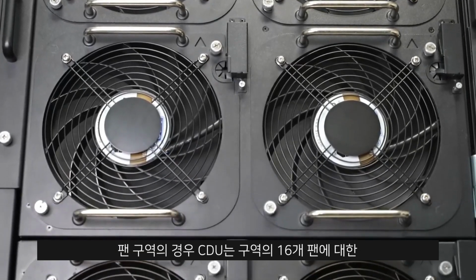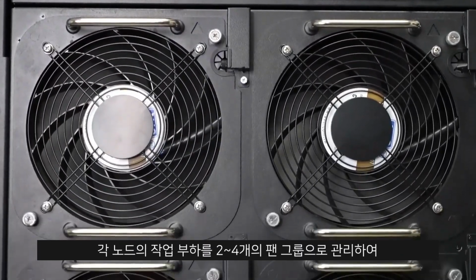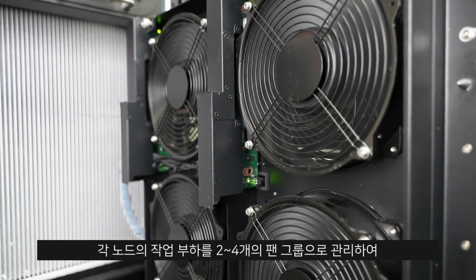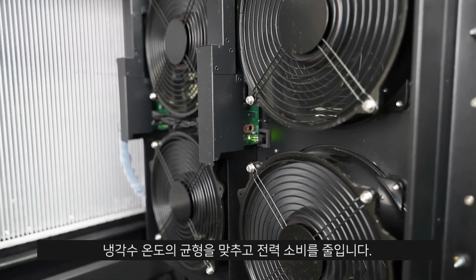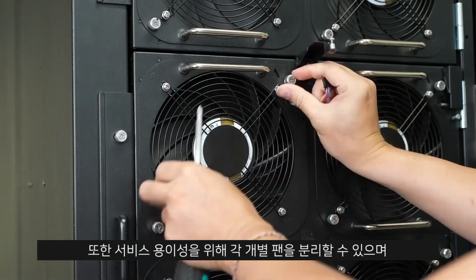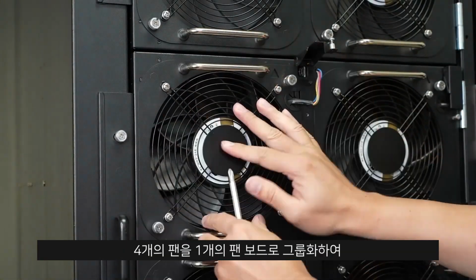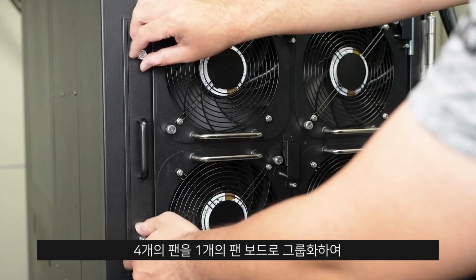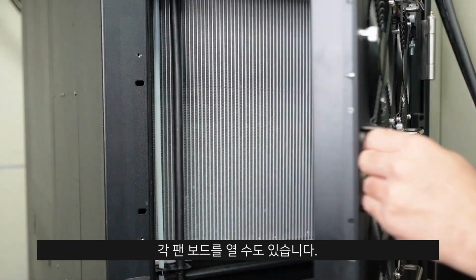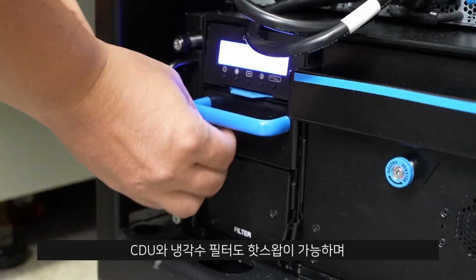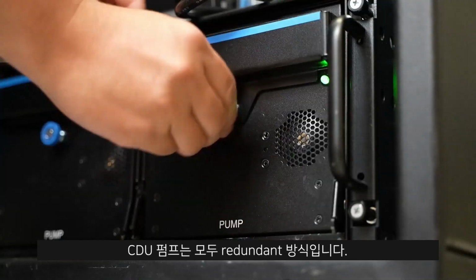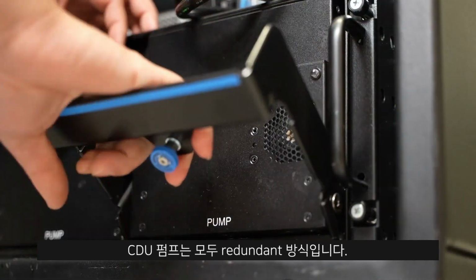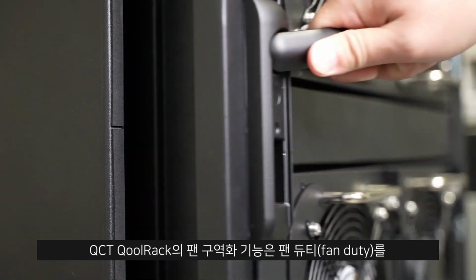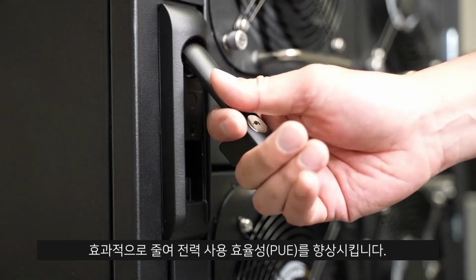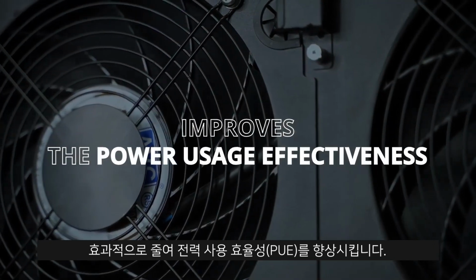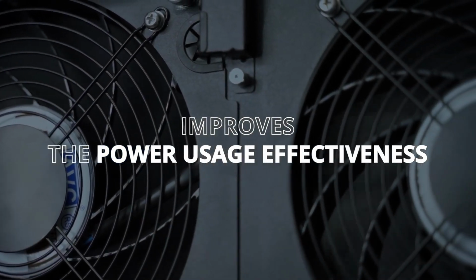For the fan zones, the CDU manages each node's workload to zone 16 fans into 2 to 4 fan groups to balance the coolant's temperature and decrease power consumption. And for serviceability, each individual fan can be taken out, and 4 fans are grouped into one fan board, where each fan board can also be opened. The CDU and its coolant filter are also hot swappable, and the CDU pumps are all redundant. The fan zoning feature of the QCT QoolRack effectively reduces fan duty, which improves the power usage effectiveness or PUE.